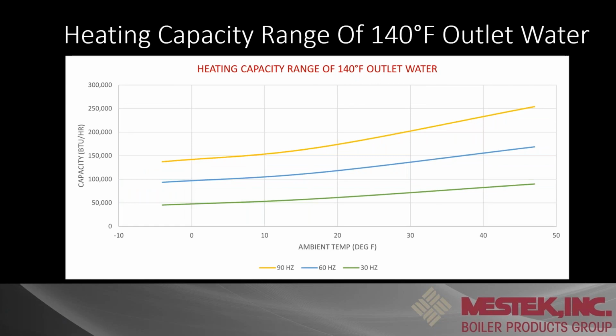Now we'll move into 140 degree outlet water. There is a price that you'll pay if you need to put out higher temps like this. On this chart, yes, we can still heat down to minus 20, but the BTUs are going to be very low at that point. But let's just look at 0 degrees outside, 140 degree water. At high speed, we're putting out about 148,000 BTUs.